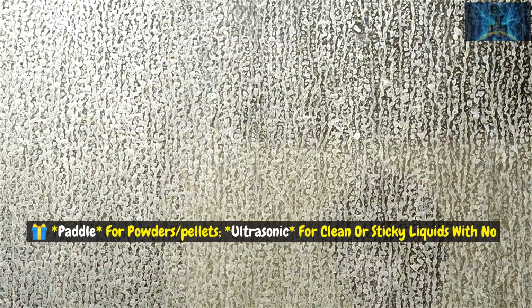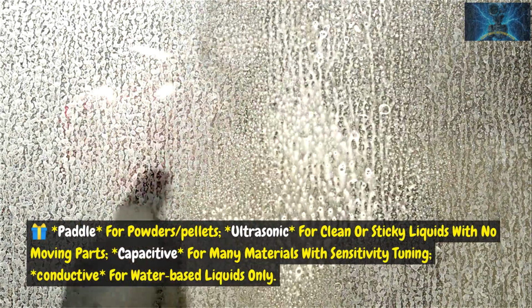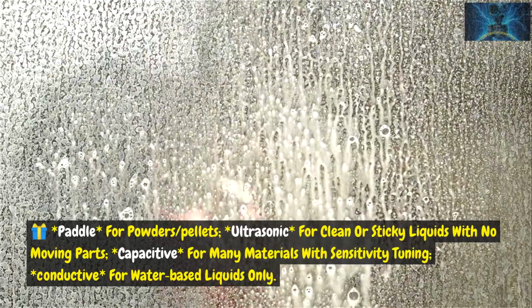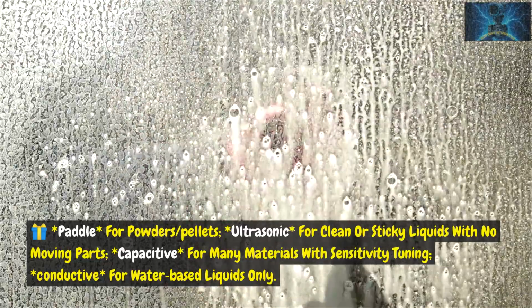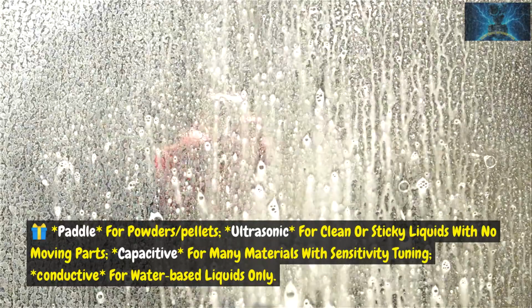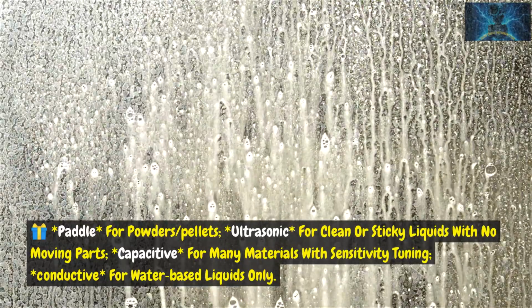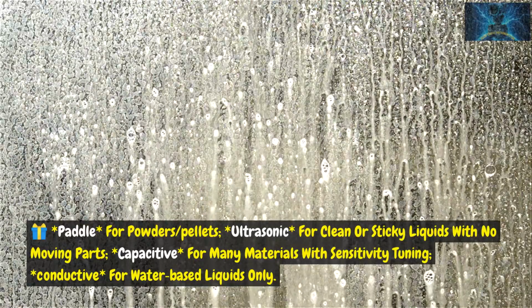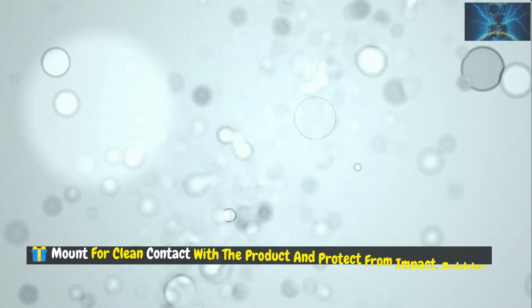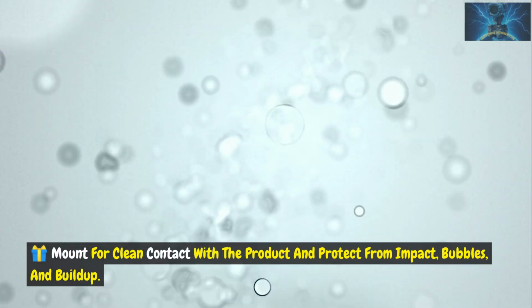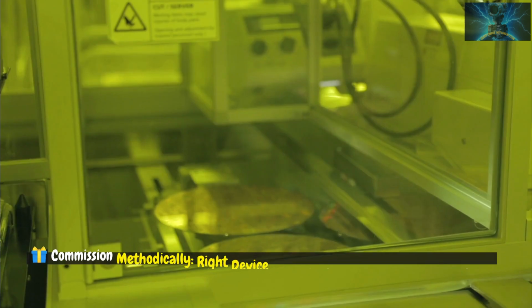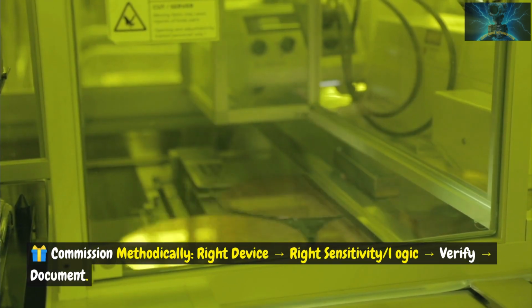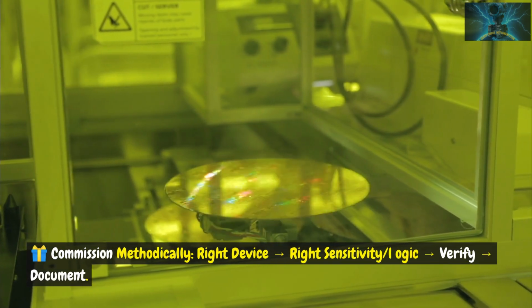many duties. Takeaways. Paddle for powders, pellets. Ultrasonic for clean or sticky liquids with no moving parts. Capacitive for many materials with sensitivity tuning. Conductive for water-based liquids only. Mount for clean contact with the product and protect from impact, bubbles, and buildup. Commission methodically. Right device, right sensitivity logic, verify, document.